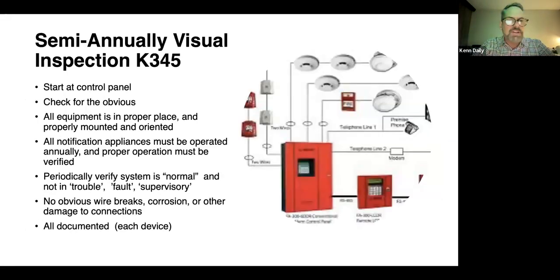So the visual inspection, of course, starts at the fire panel, and then would run to every single one of your devices in your building, whether it's the fire alarm panel itself, the smoke detectors, pull stations, or the dialing system, because obviously, most of you know you have to have 2 dialing systems out. That's why we call it a monitored fire alarm system. Now, many of you, including my own building, have one of those dialers as a cellular connection, so that basically the cellular connection is maintained at all times to send a signal if necessary.